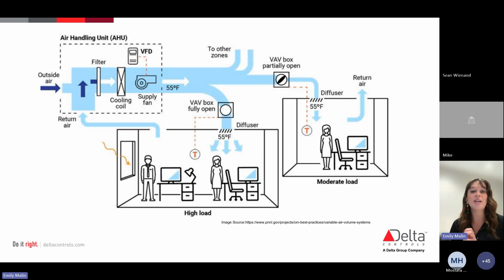So what's happening, you can see on there that the VAV box is fully open. So that means it's pulling more air into the space. Whereas we might have our lovely gal up there in our moderate load that is saying, hey, there's no window, there's only one heat source. So our VAV box could be partially open, or it could even be in that deadband mode if we're right at that set point that we need to be in that zone. So this is really how all of this is working together in those control loops in order to maintain that energy efficiency and occupancy comfort.